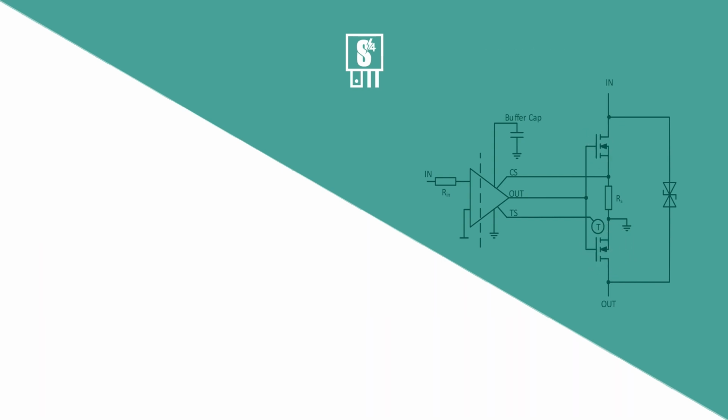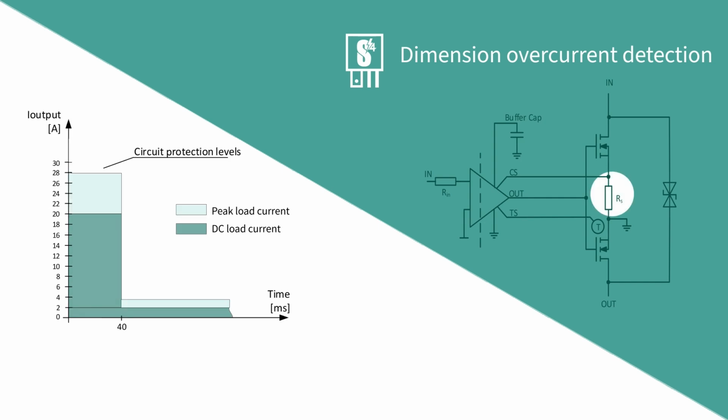Moving on to the fast overcurrent shutdown, it is important to properly dimension the shunt resistor. Note that the SSR outputs for SSR applications must comply with the AC15 requirement of standard IEC 60947-5-1. This leads to an overcurrent detection threshold of a minimum of 10 times the nominal current, with an additional factor of square root 2 for the peak value.